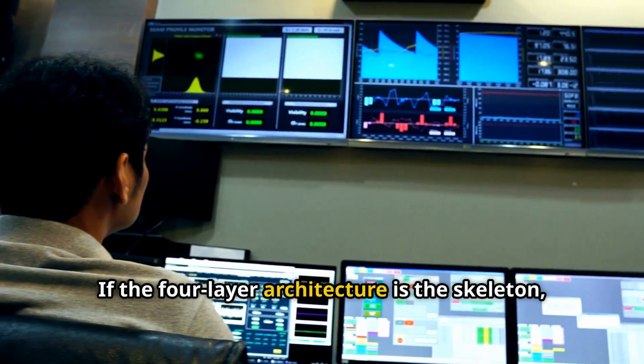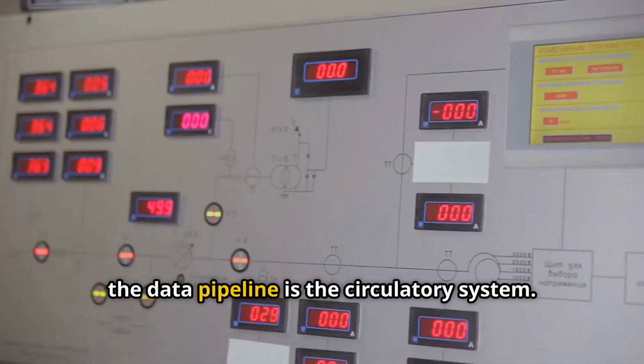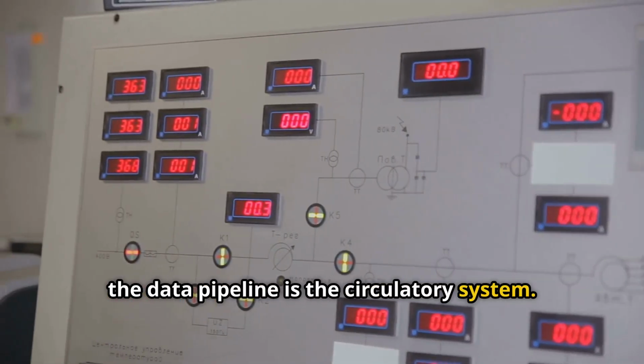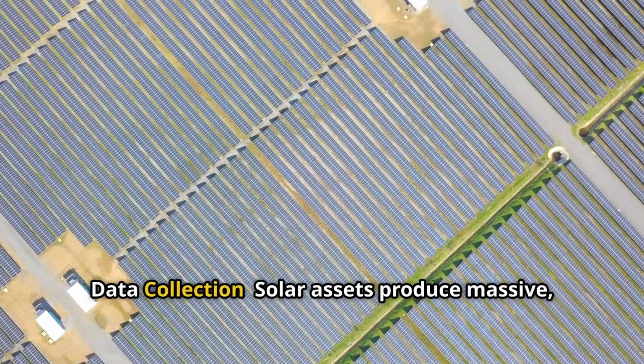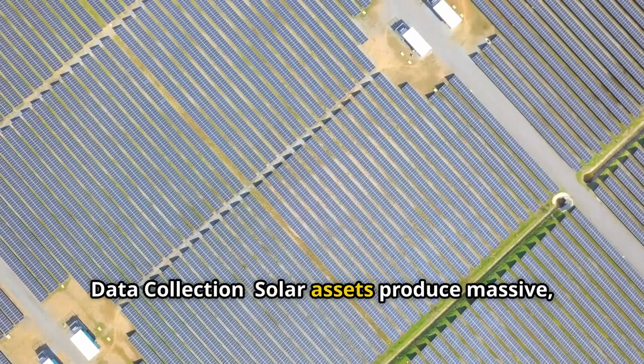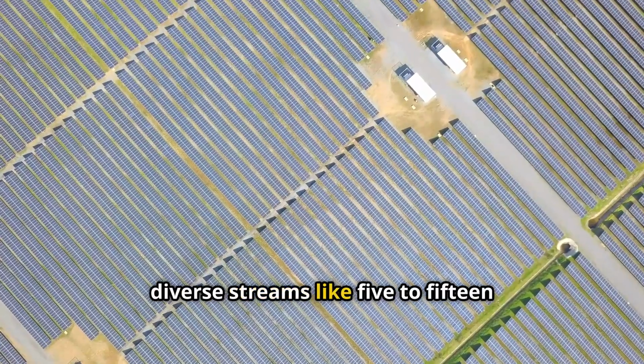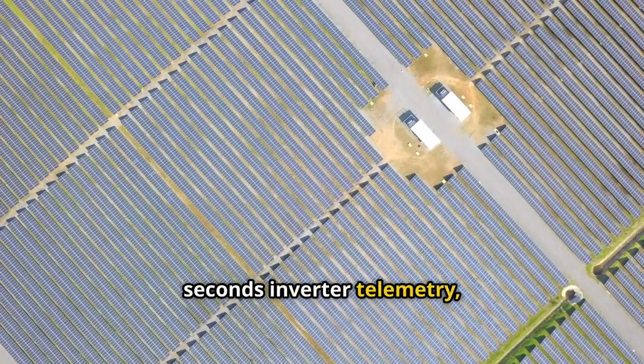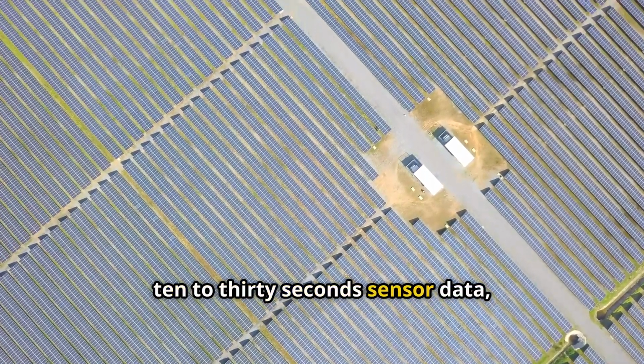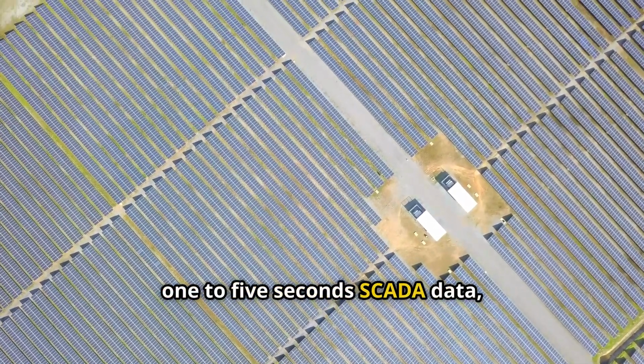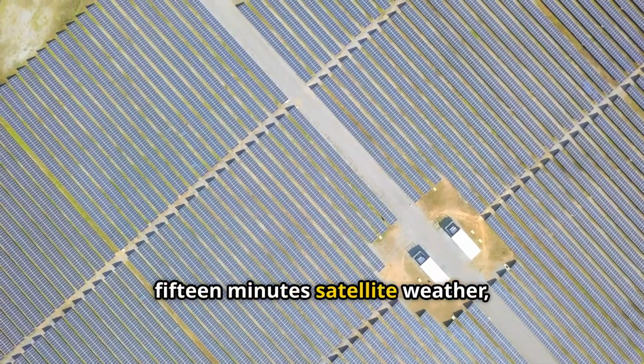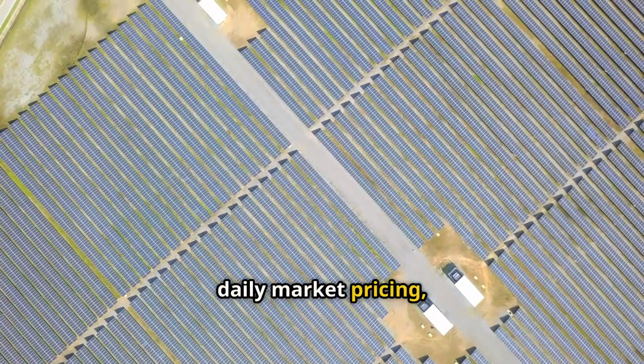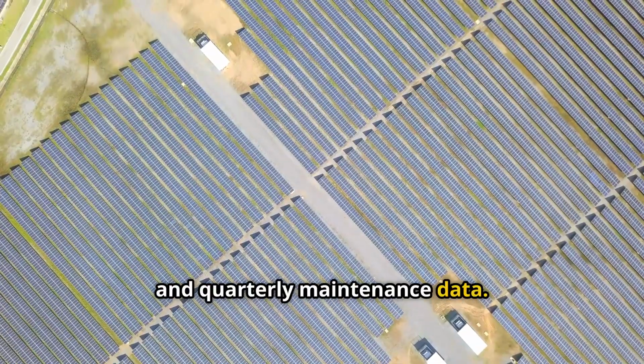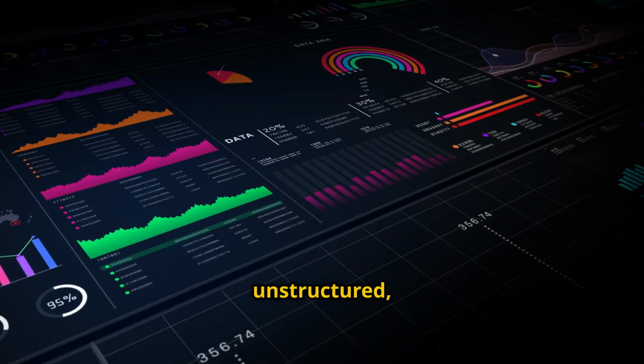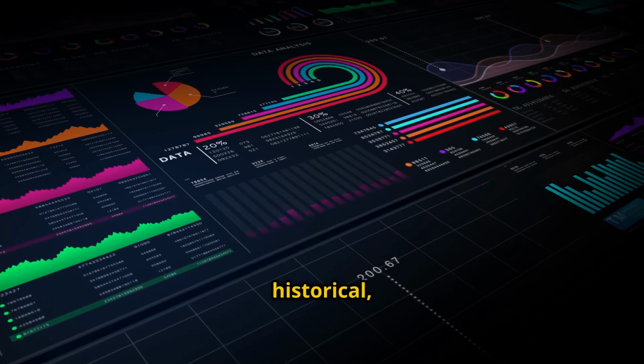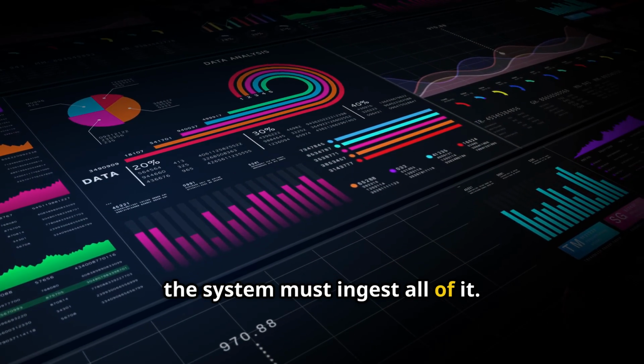If the 4-layer architecture is the skeleton, the data pipeline is the circulatory system. Data collection. Solar assets produce massive diverse streams like 5 to 15 seconds inverter telemetry, 10 to 30 seconds sensor data, 1 to 5 seconds SCADA data, 15-minute satellite weather, daily market pricing, and quarterly maintenance data. Structured, unstructured, real-time, historical, the system must ingest all of it.